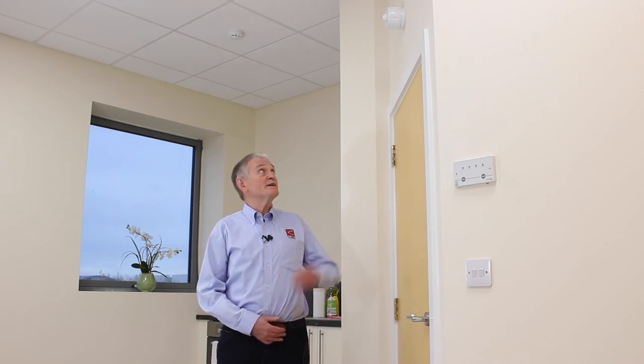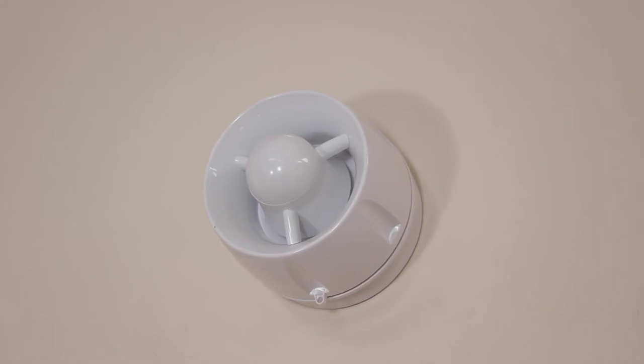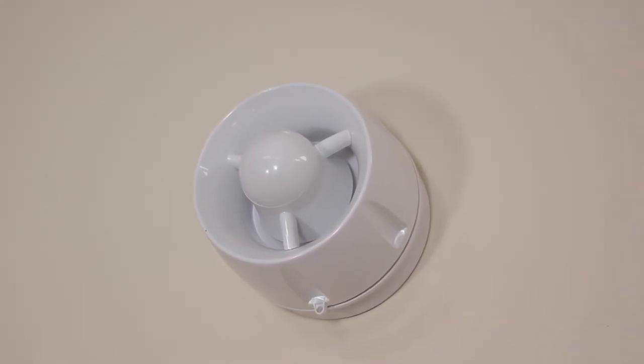Now let's take a quick look inside a flat. BS 8629 says that most flats will only need a single evacuation sounder which should be installed near the entrance. CTEC's alert sounder is one of the loudest and most efficient on the market and it also has a self-test function that avoids the need to listen to the sounder in each flat during annual maintenance. If necessary, more sounders, visual alert devices and even vibrating pillow pads can be fitted.